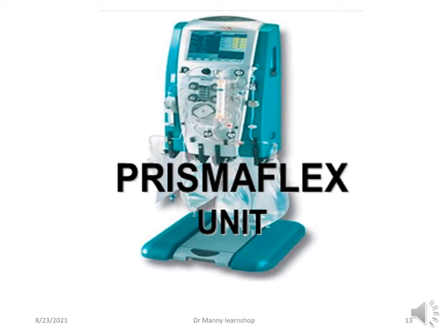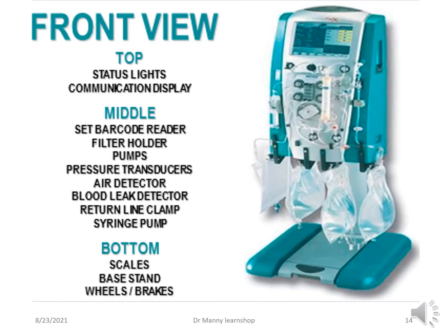Now let's review the Prismaflex unit itself, not in a lot of detail, but just to give you an overview as to how this machine functions. The front view has status lights and a communication display. The middle has a set barcode reader, filter holder, pumps, pressure transducers, air detector, blood leak detector, return line clamp and syringe pump. And at the bottom are the scales, the base stand, the wheels and the brakes.